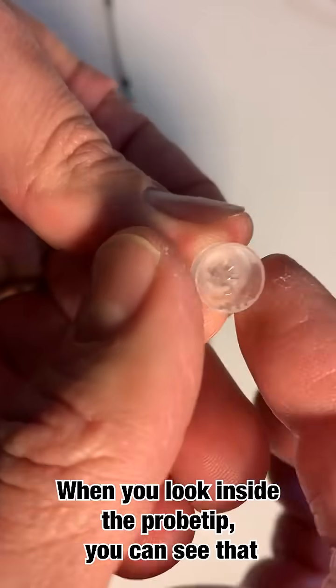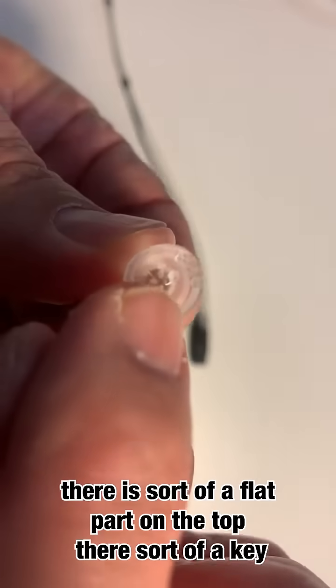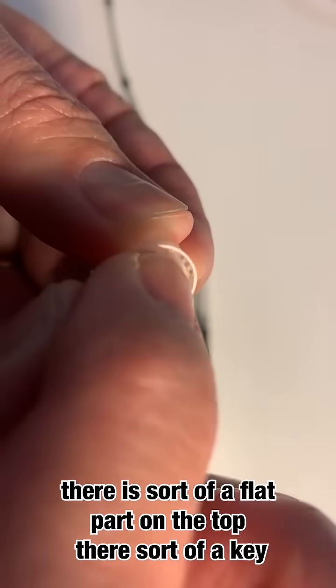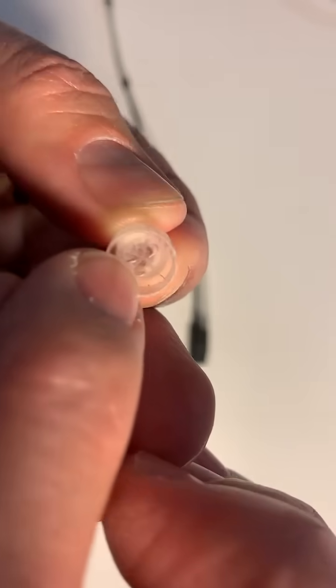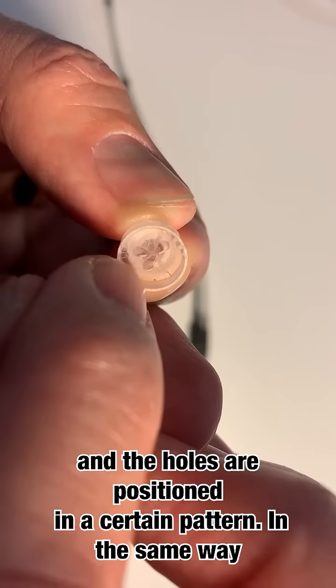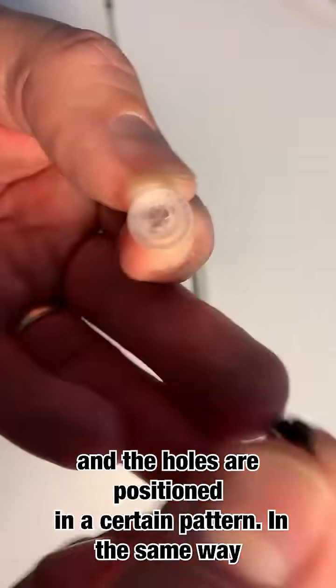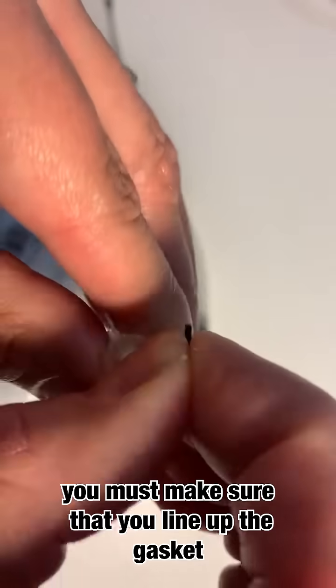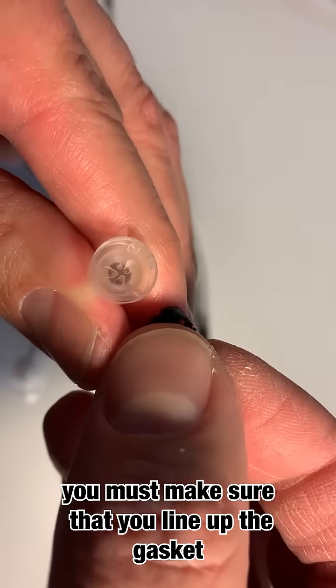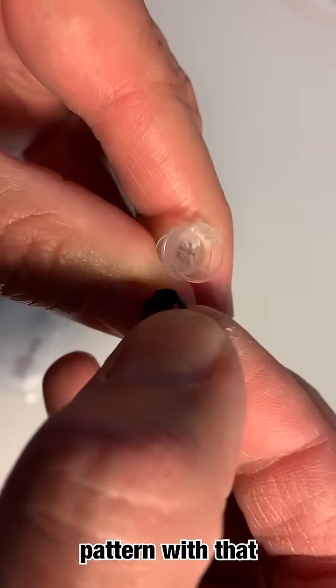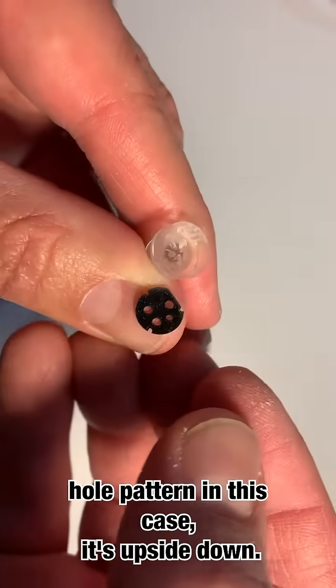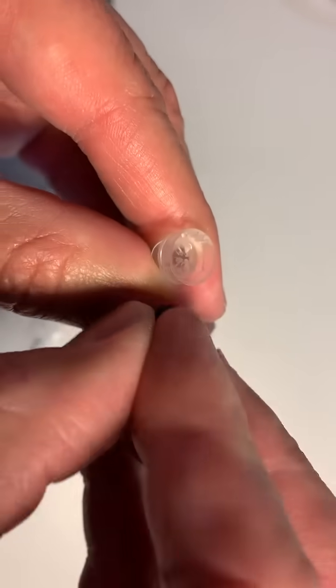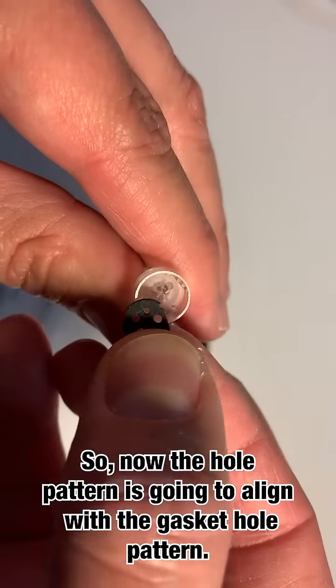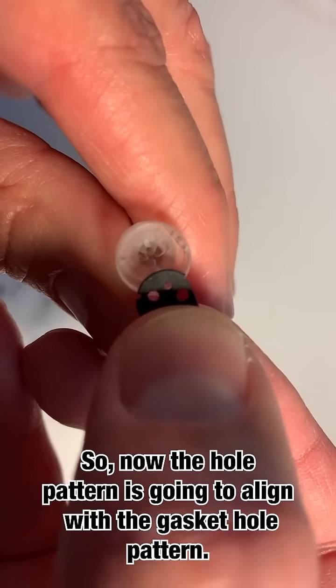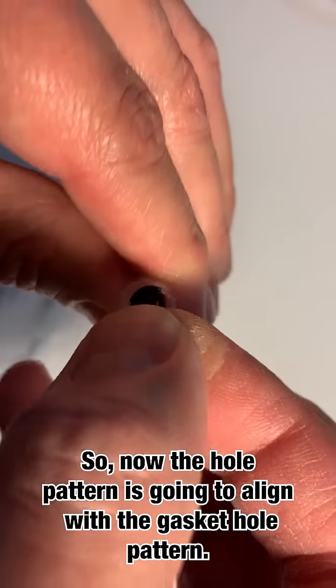when you look inside the probe tip, you can see that there is sort of a flat part on the top there, sort of a key, and the holes are positioned in a certain pattern. In the same way, you must make sure that you line up the gasket pattern with that hole pattern. In this case, it's upside down. So now the hole pattern is going to align with the gasket hole pattern.